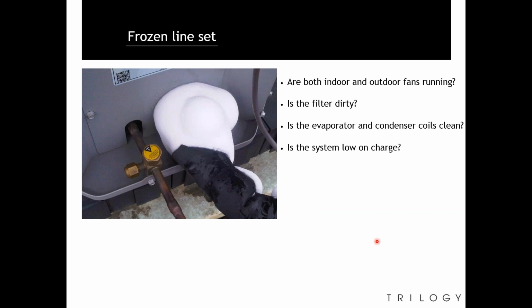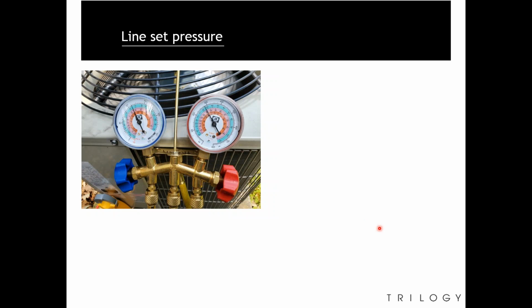Now the unit's not necessarily low on freon. If there's poor to no airflow, the unit will freeze up. So you always want to make sure the fans are running and the coils are clean before we throw our gauges on. If we have a frozen line set, before we can hook up our gauges, that system will need to thaw out before we can get an accurate reading of our pressure. We also want to let our system run for about 10 minutes to regulate.